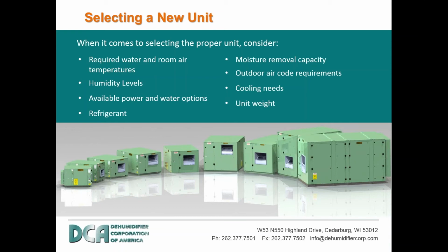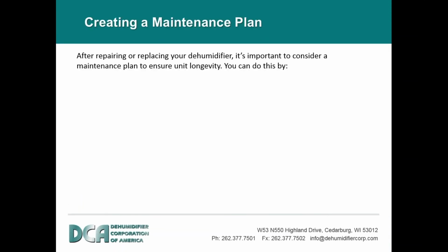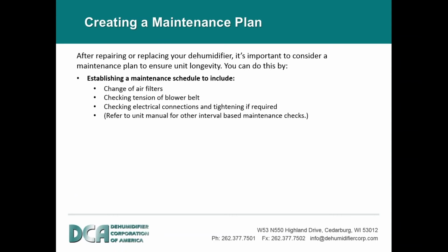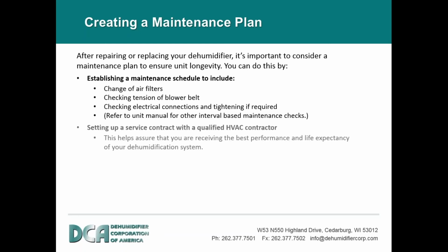An important part of caring for your dehumidification system is to create an effective maintenance plan. You can do this by simply establishing a maintenance schedule to include the changing of air filters, checking tension and replacing the belts, tightening all the electrical connections. You can see the owner's manual for a list of these and a lot more. Many times it makes good economic sense to make use of service contracts offered by qualified HVAC installers and service contractors, assuring that you are receiving the best performance and life expectancy of your dehumidification system.